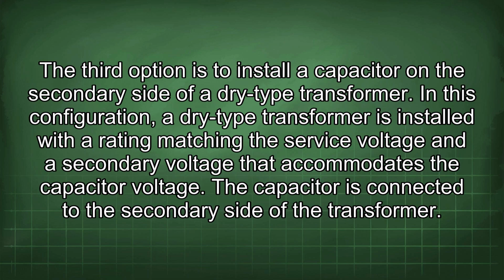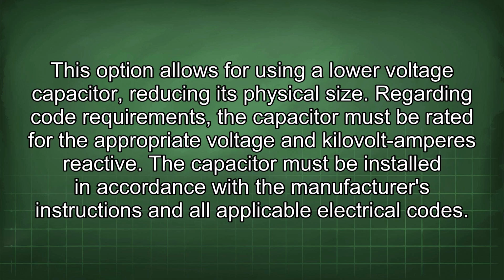The third option is to install a capacitor on the secondary side of a dry-type transformer. In this configuration, a dry-type transformer is installed with a rating matching the service voltage and a secondary voltage that accommodates the capacitor voltage. The capacitor is connected to the secondary side of the transformer. This option allows for using a lower voltage capacitor, reducing its physical size.